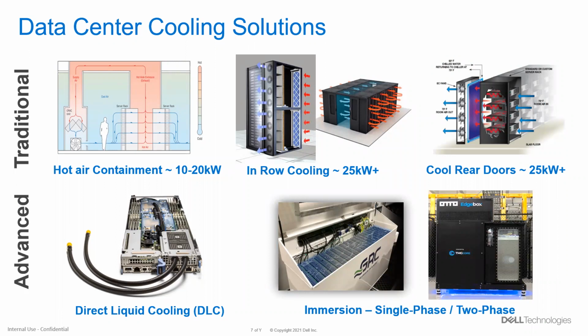So Dell's perspective on liquid cooling is that we want to support customers at whatever stage they're at, whatever rack power densities they're at. It's all about what's most relevant for you and what's the most efficient and appropriate solution for the IT that's running your workloads. Today, the vast majority of customers are still implementing solutions that fit on the traditional line, which is using air, being smart about containment. The separation between hot aisle and cold aisle in your data center is a fundamental starting point. There are ways to augment your air-cooled data center using in-row cooling or using rear doors, which use liquid to do the heat capture again, but are spot solutions. And what I mean is you can place these in a particular area of the data center that needs help.